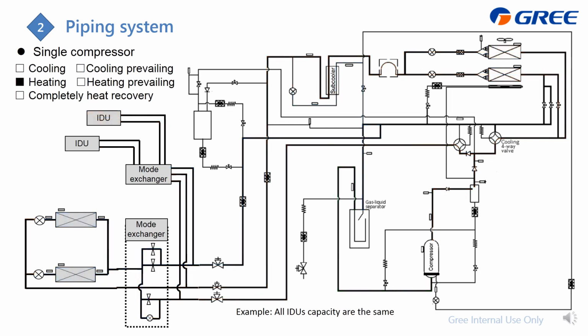Next, we go to the heating mode. This time, we just assume these 2 indoor units require heating, and then the hot gas from the compressor will go through this heating four-way valve, and then we offer this hot gas directly to the mode exchanger, and then we just turn on this 2, which is the solenoid valve and the EXV, to offer the hot gas to the indoor unit, which will make it release heat, which is doing heating, and then the hot gas will become liquid and go to this indoor unit EXV.